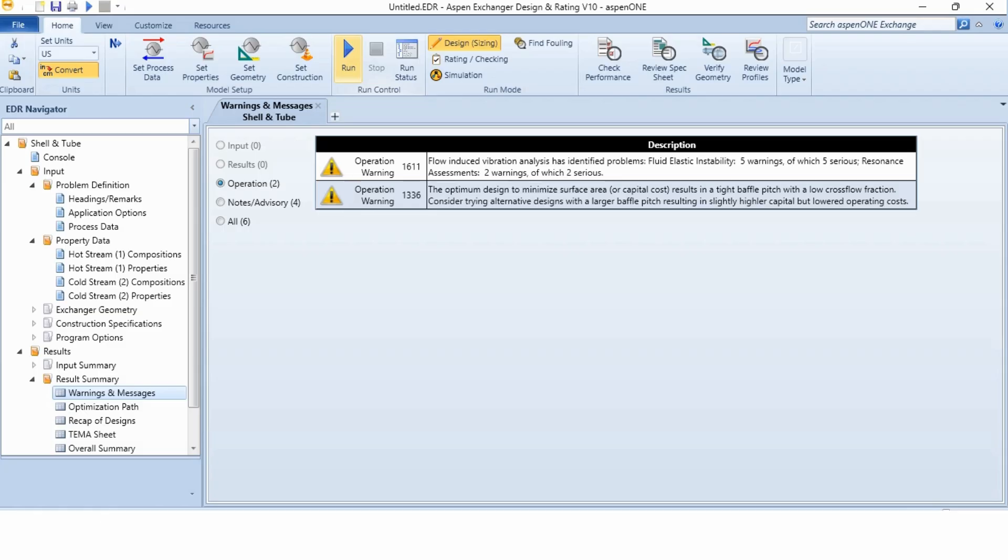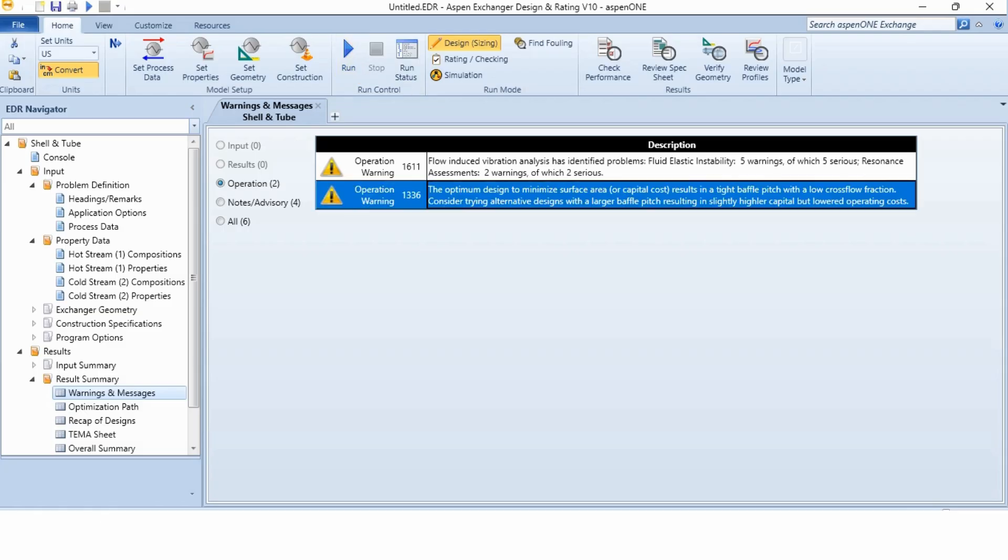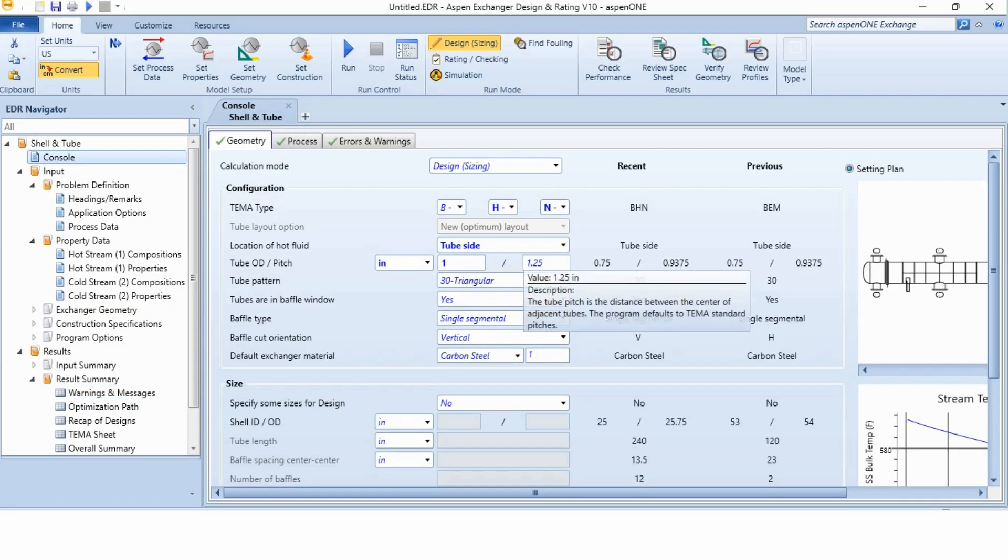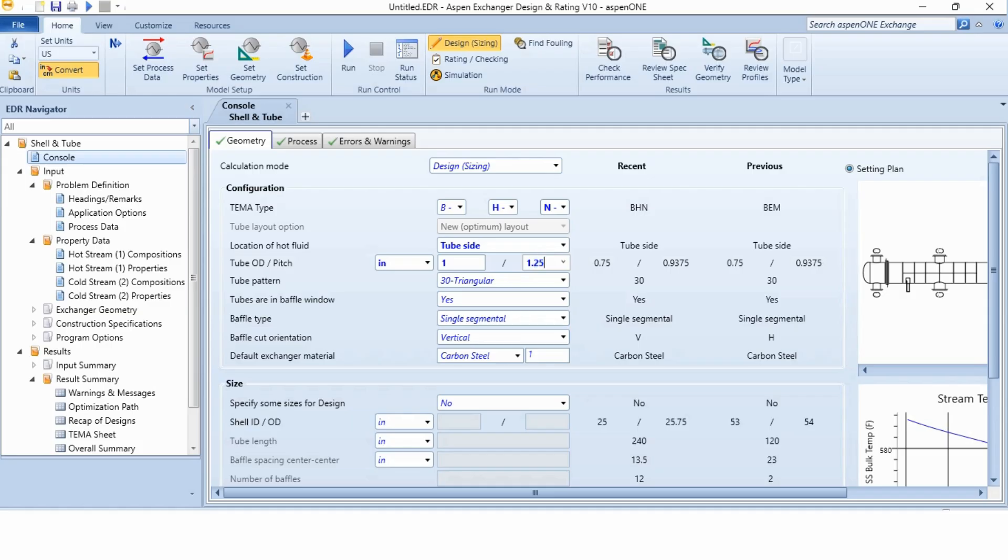Now, the results have no issues but there are still warnings which are involved in the system. So, again, we have to make some changes. The changes which I am proposing here that you change the tube OD and pitch from 0.75 and 0.9375 to 1 and 1.25 respectively. Obviously, the unit is inches.